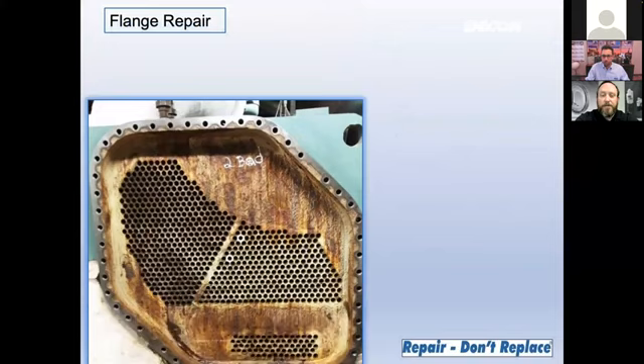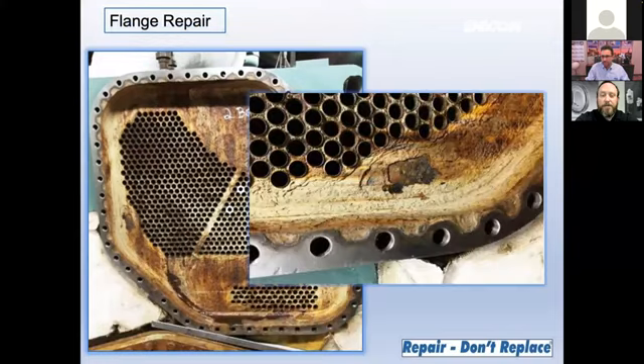While full tube sheet and water box high build applications comprise the vast majority of the heat exchanger applications we undertake, some of our customers just need to get their existing equipment back in service. In many of these instances, leaks caused by erosion corrosion of the flange areas underneath the gasket surfaces of the tube sheets and water box get so badly corroded that it prevents the equipment from being buttoned up and put back in service. Over time, water has undercut the flange gaskets, eroded and corroded the metal, eventually preventing the units from keeping a seal when put back together.